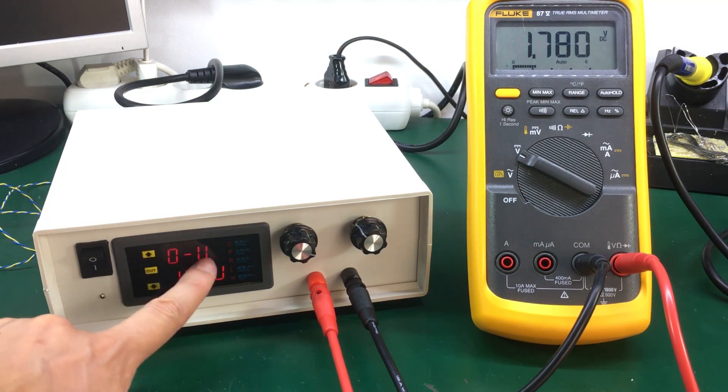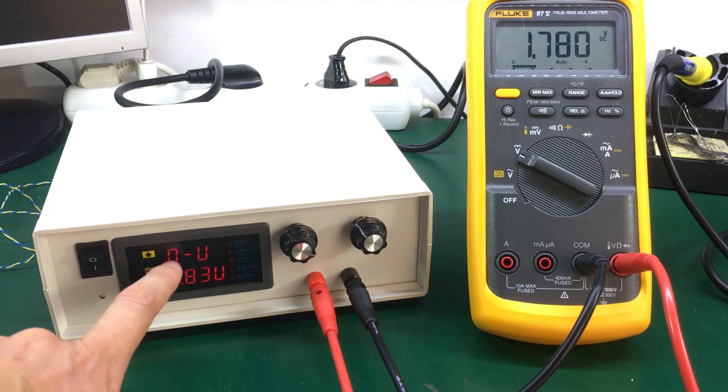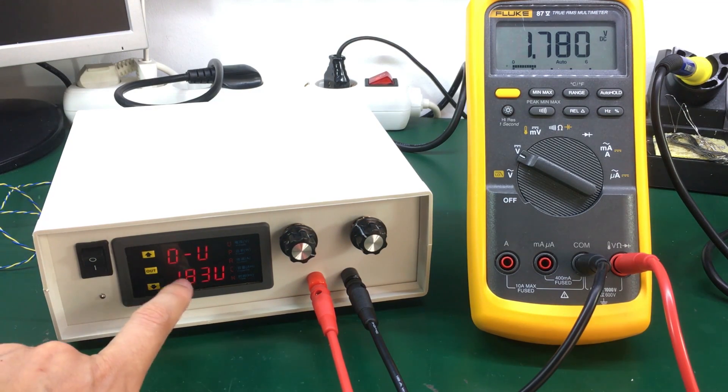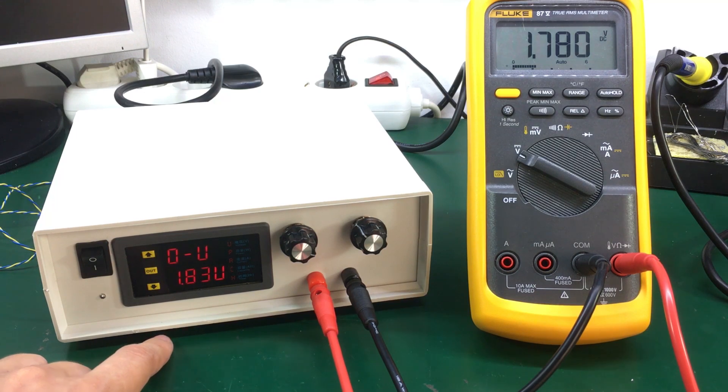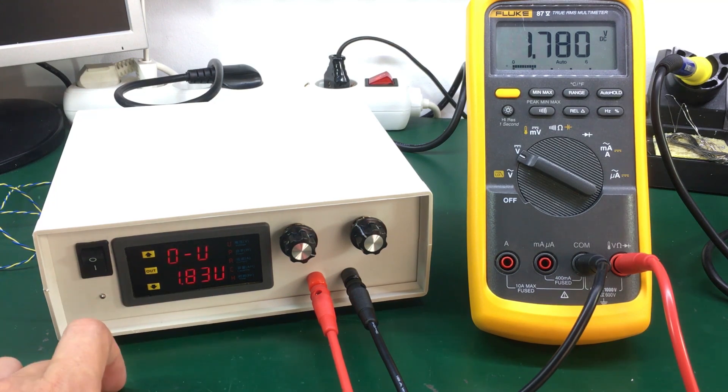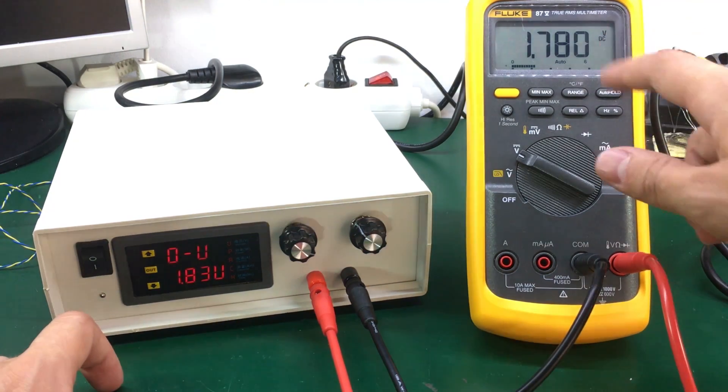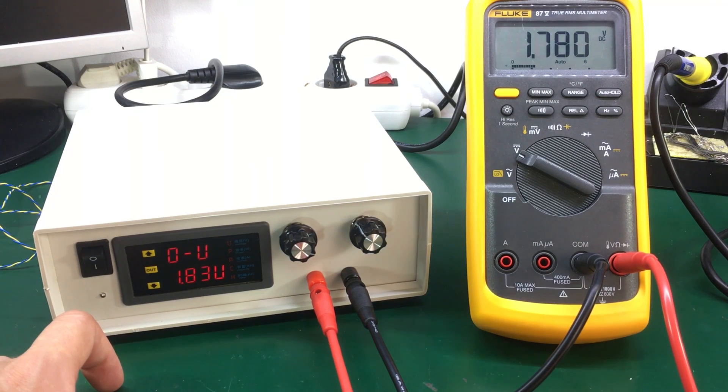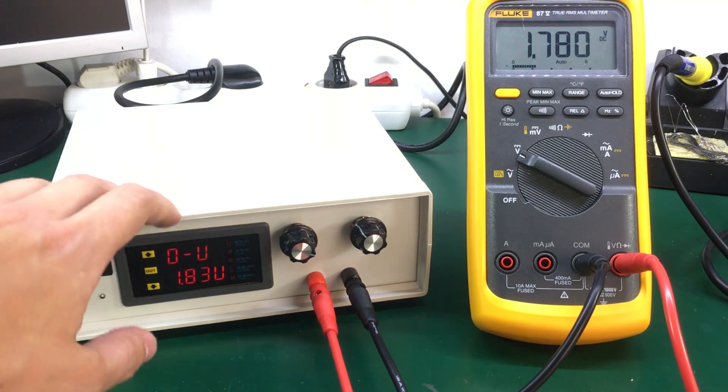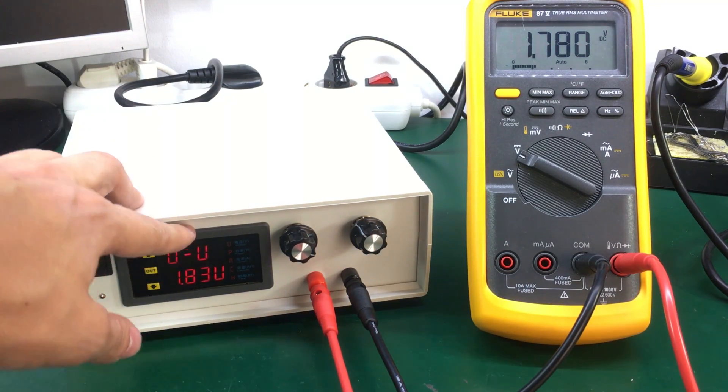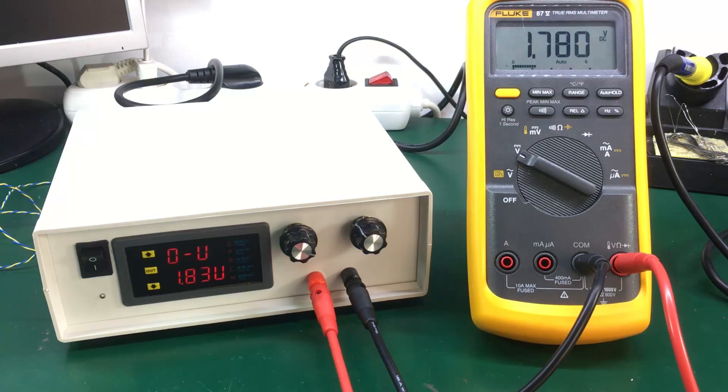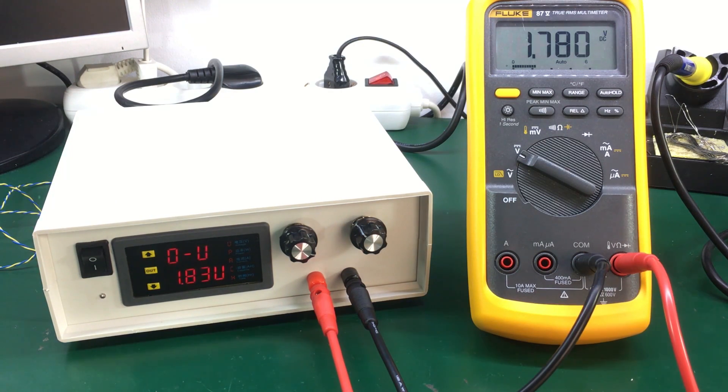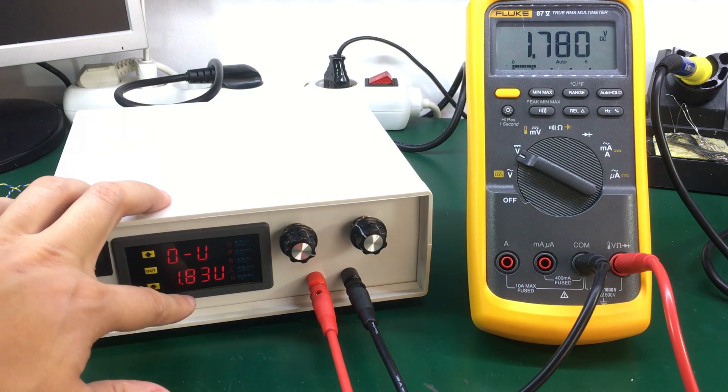I'm going to press and hold the out button until this is showed on the screen and right now we are in the voltage calibration mode which is menu 0 and we can use the up and down arrows to calibrate for this voltage until we get the same value as on the multimeter.